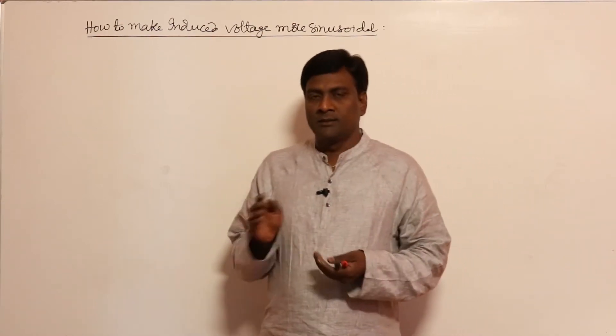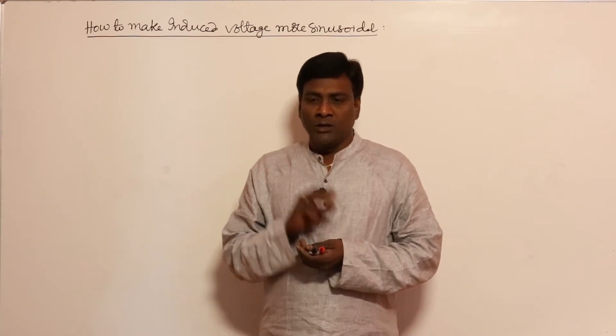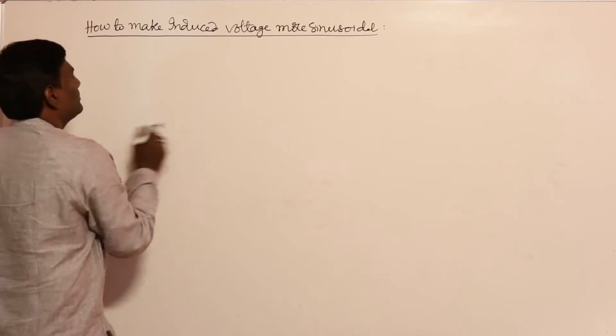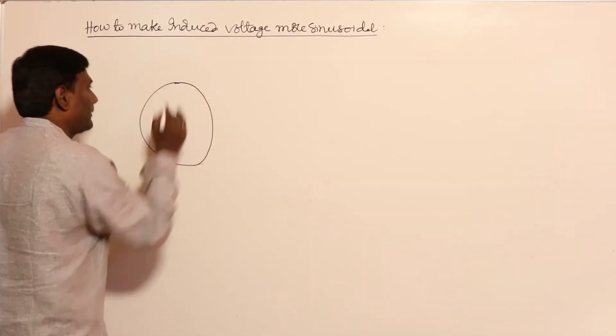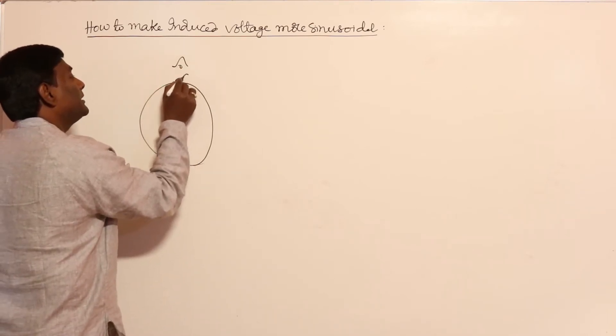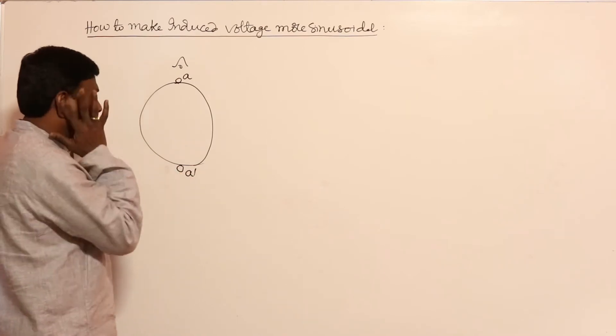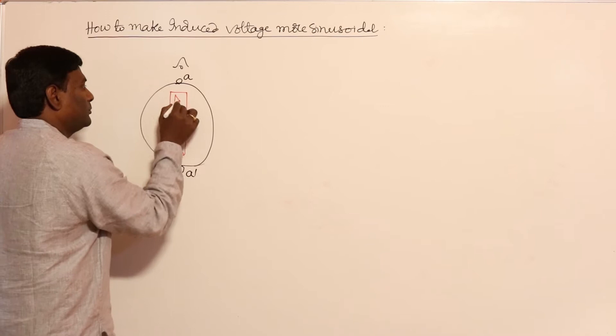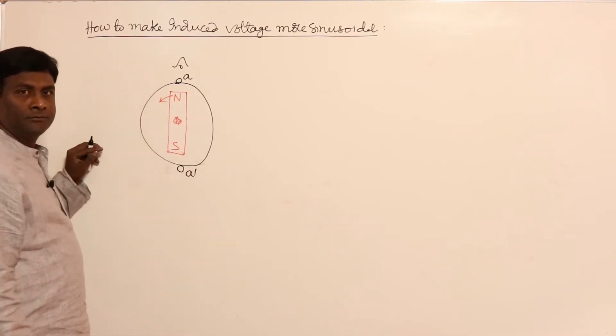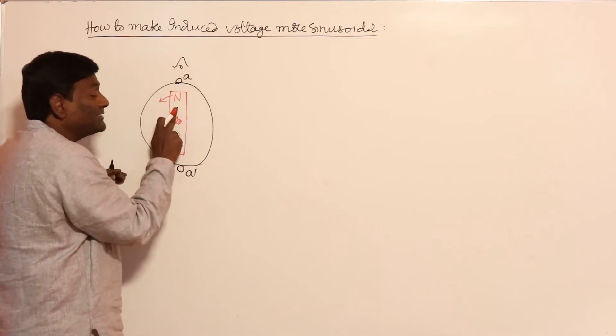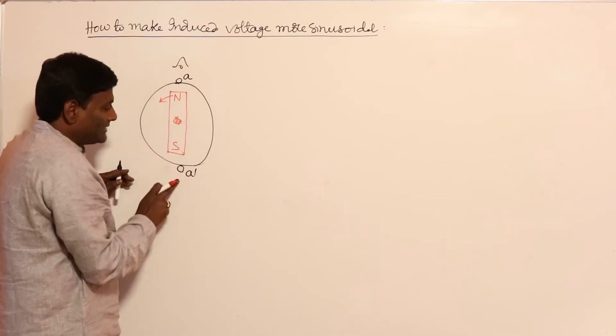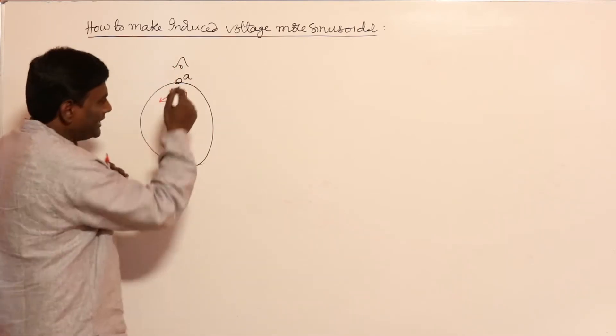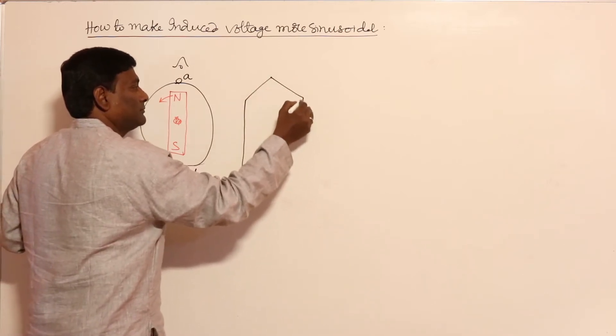To make induced voltage more sinusoidal, we can use short-pitched coils to reduce harmonics. For example, consider a stator with a two-pole machine. If conductor A is under the flux density maximum of the N pole, and A-dash is under the flux density maximum of the S pole, then if positive maximum is induced at A, negative maximum will be induced at A-dash.